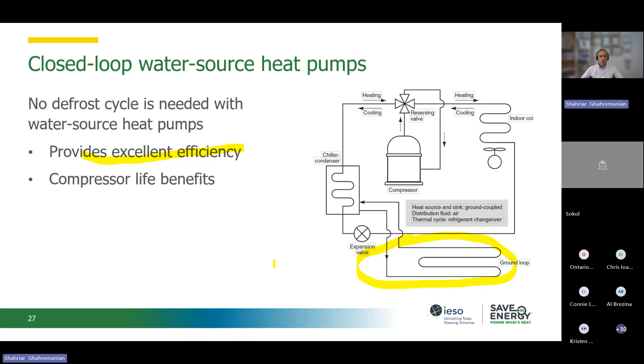So for larger buildings actually, the ground coupled or closed loop heat pumps make more and more sense, because the installation cost of ground source or water source heat pumps can be a little bit high for a single residential family. So for a larger building like a condo and those kinds of towers, it makes more sense actually. And then their system becomes much smaller. They need just the pumps and a refrigerant going to the ground and bringing back the heat during the winter season or rejecting the heat during the summer season actually.